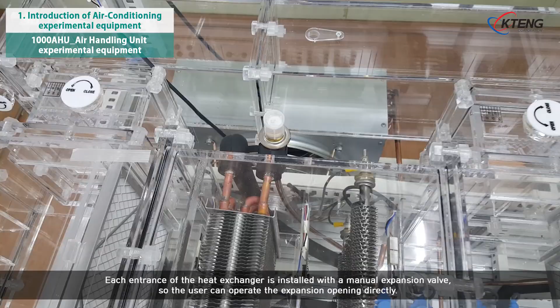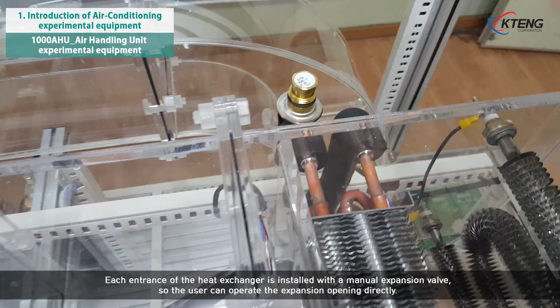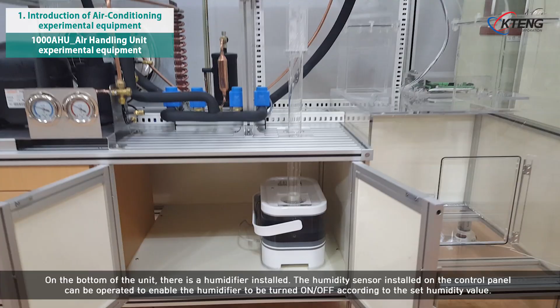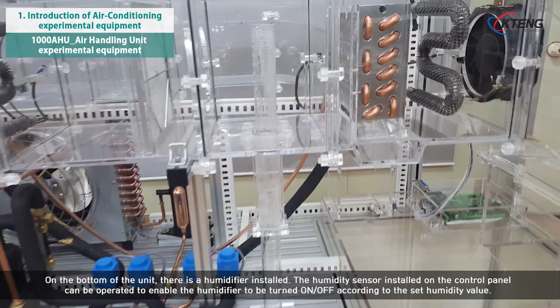Each entrance of the heat exchanger is installed with a manual expansion valve, so the user can operate the expansion opening directly. On the bottom of the unit, there is a humidifier installed. The humidity sensor installed on the control panel can be operated to enable the humidifier to be turned on and off according to the set humidity value.